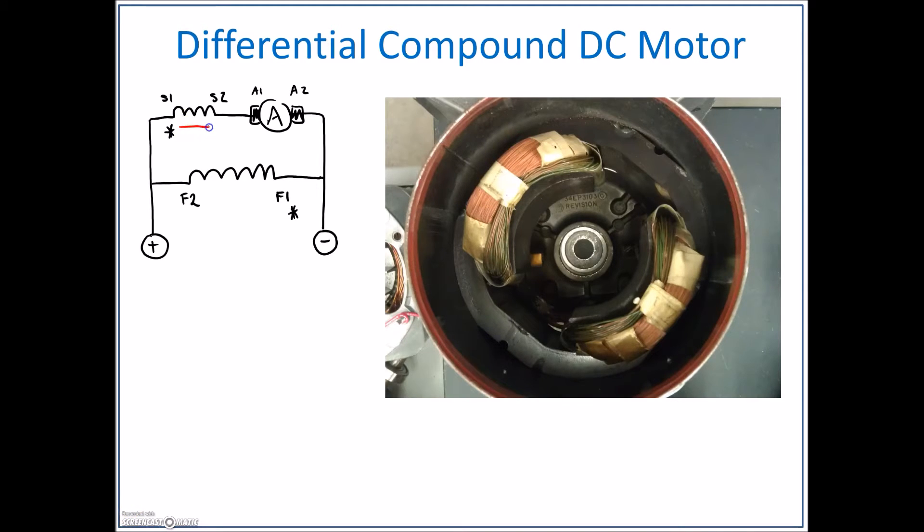If those two magnetic fields are going in opposite directions, then one is going to cancel the other one out, and that's why the name of this connection is the differential compound DC motor. This is not a connection that we're looking for whatsoever.